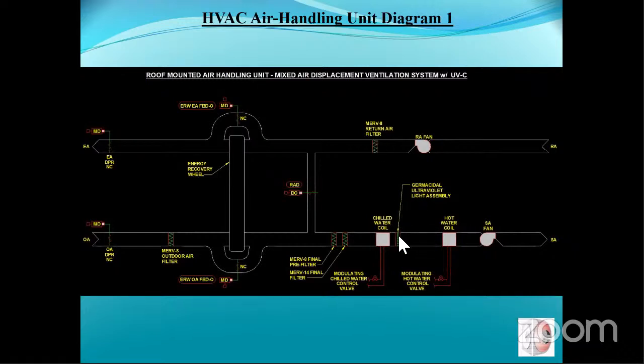So this diagram is mostly to help everybody get a good understanding of the airflow direction and where these components would be placed within the units. Bottom left, that's where your outside air enters the unit. It hits a MERV 8 pre-filter, and under normal operation, it would go through the energy recovery wheel. So the filter just protects the wheel from outdoor contaminants. The air then travels and mixes with return air. And then that mixed air will go through the MERV 8 pre-filter and MERV 14 final filter before entering the chilled water coil to be subcooled.